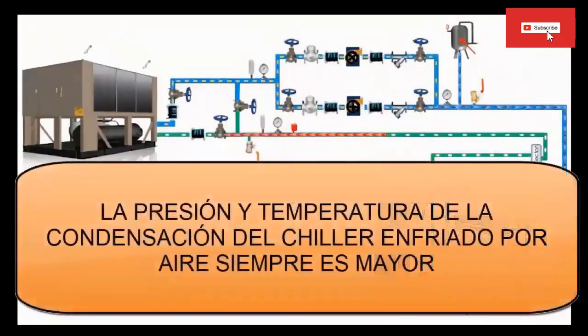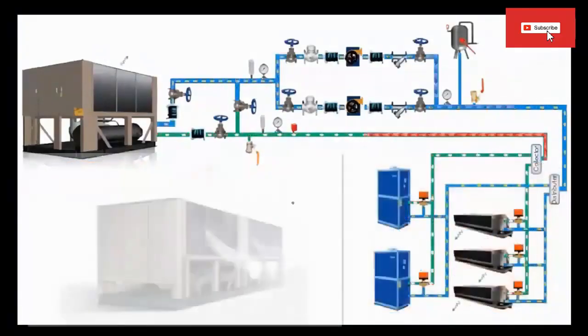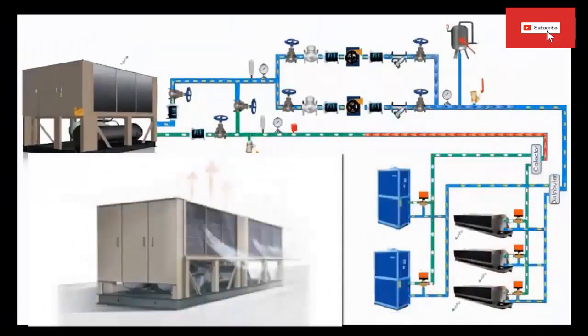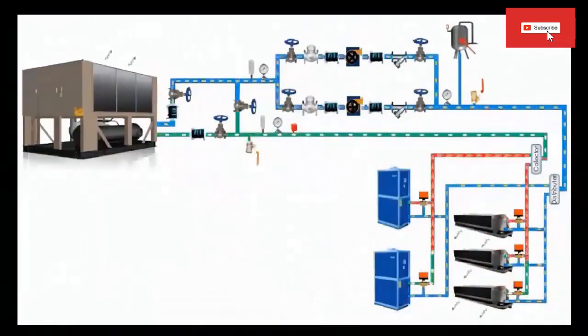Always remember that the lowest temperature that the refrigerant can reach when leaving the condenser of an air-cooled chiller is the dry bulb temperature of the environment where it is installed, while in the water-cooled chiller, it is the wet bulb temperature. It is very important that the fans of the air-cooled condenser chiller are in very good condition, thus avoiding stress on the compressors.